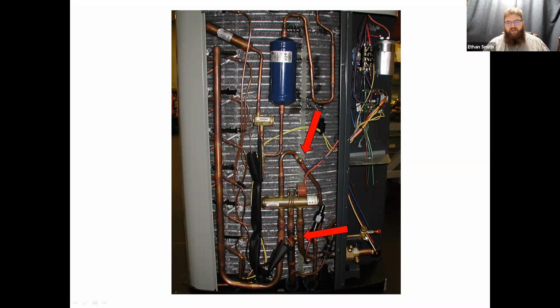Okay. The liquid line is going to be a little different because that's the return from the indoor coil, so that pressure and that pressure are going to be different. You're going to have some pressure drop through the indoor coil. That's normal. So my recommendation to guys is always, if you're in heating mode and it's a heat pump, gauge up at the reversing valve, not at the line set connections. I always love taking that call where I get the panicked technician who says, oh, my compressor's dead, I've got the same pressure, and he's gauged up in heating mode outside on the service ports. It's because they're both on the same side of the system.